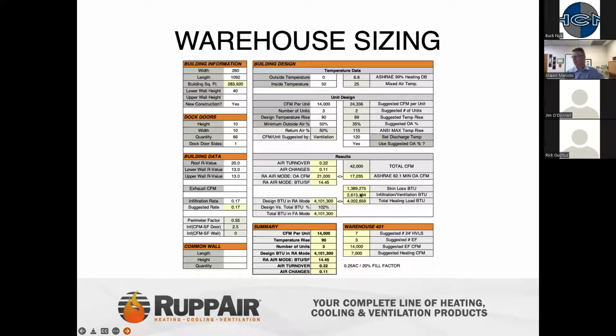From there, basically the calculator is going to give you everything from what the heat is needed to heat the space and what our equipment we've selected is going to offer to heat the space. So again, 4 million to heat it, we're about 4.1, a little bit extra heat available to them. Like I said, down here is your summary of what equipment we needed. 3 heating units at 14,000 CFM, 90-degree temperature rise. In this case, this is the spec that basically the client was looking for, a 0.25 air change rate along with a 20% fill factor. This is actually a client we do a lot of work with that recognizes the benefits of having ventilation both in a spec building and in an occupied building.